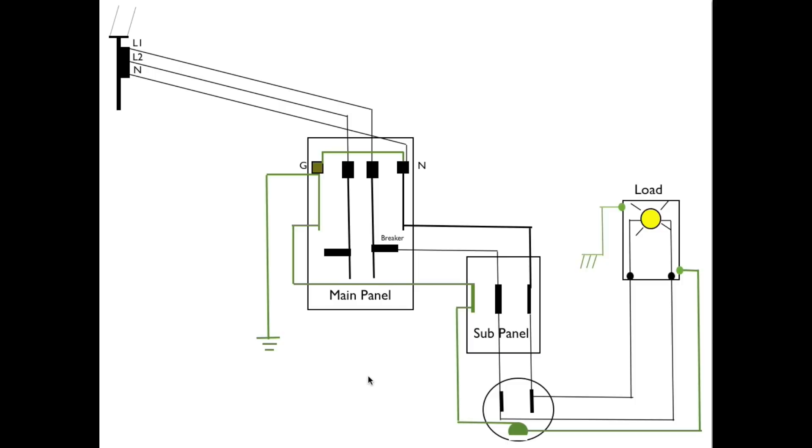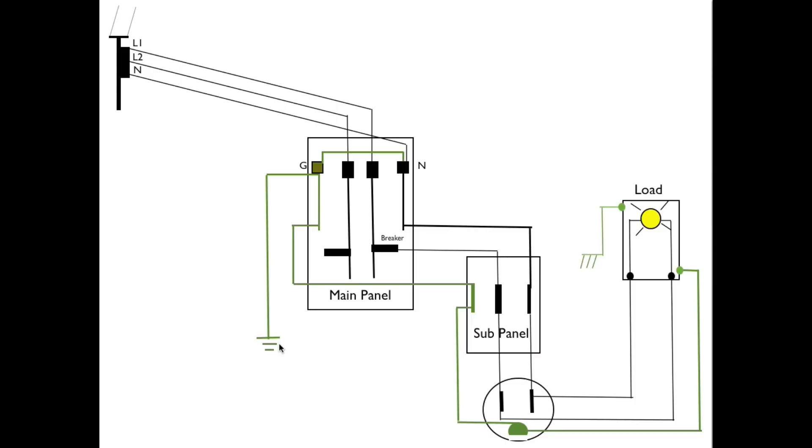I hope this makes a little more sense. It took me years, years to figure this silly thing out too, because I couldn't figure it out either. But main panels, we tie the neutral and the ground together so that we can go to the ground. By the way, that ground here, that's usually a ground rod or it can be a water pipe. Now, there's a bunch of different codes on this, but you usually have to have a separate ground rod, not just a water pipe. So, anyway, I hope this makes sense. So many questions if it doesn't.